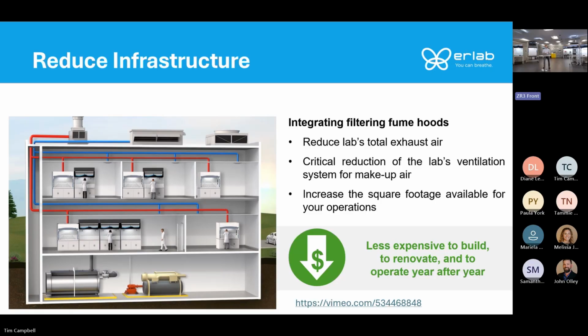And not to mention, you're going to be able to stay at that prescribed air change rate. You're not going to overventilate the space. So you're going to have significant energy savings if you design the lab up front as a combination of ducted and ductless. On a project with 77 ductless fume hoods throughout 6 different teaching labs, they were able to reduce the size of their chiller by 260 tons. That was hundreds of thousands of dollars we saved up front, as well as moving forward for the maintenance of that chiller. It's much less expensive.